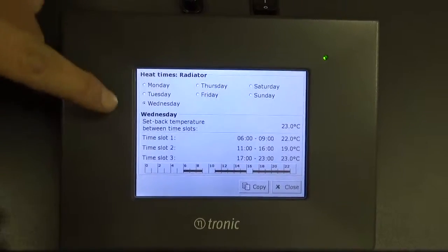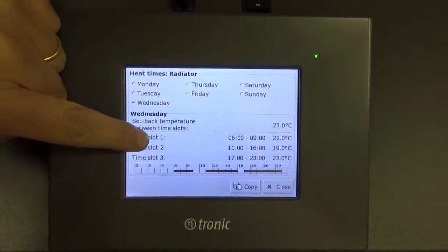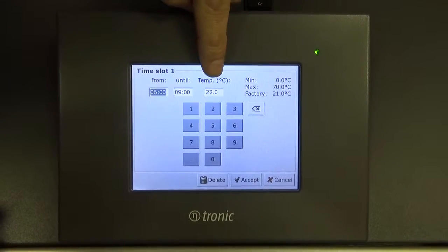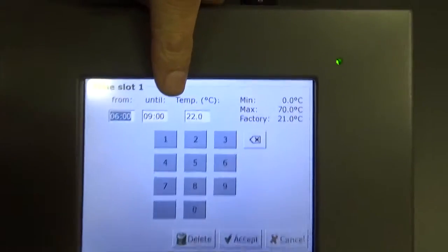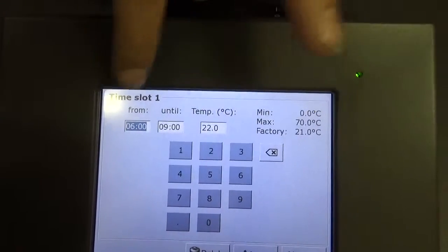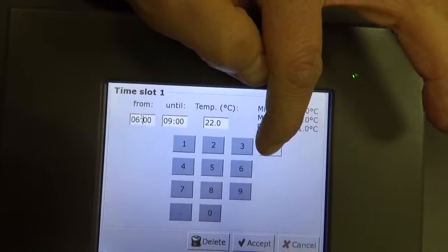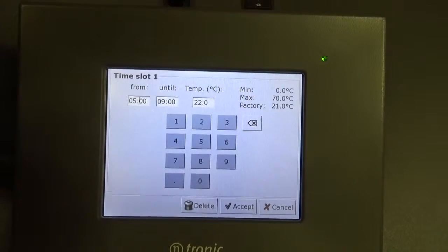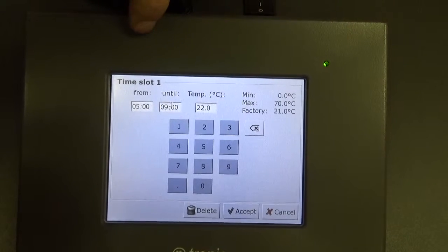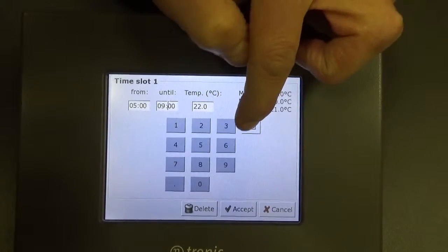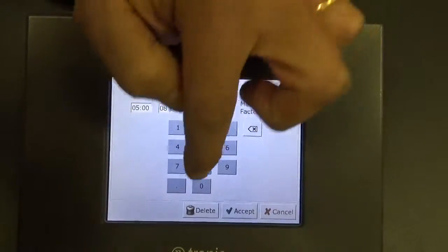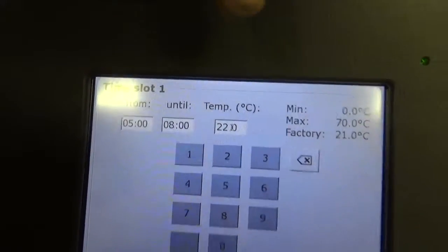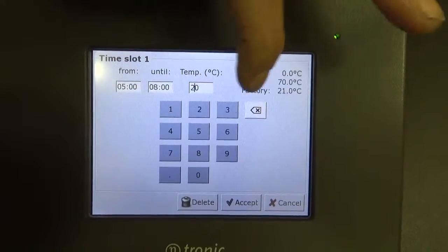The way we do this is we choose one day — at the moment we've chosen Wednesday. If we click on time slot one, you'll see that it's currently set to come on at six o'clock, go off at nine o'clock, and in between those two times the target temperature is 22 degrees. We can change the start time by clicking on the window and using the delete button to change the time. I can put in, for example, 05:00 — five o'clock in the morning — and then change the off time to 08:00. The target temperature can also be changed by clicking on the text box; I can change that to, for example, 23 degrees.